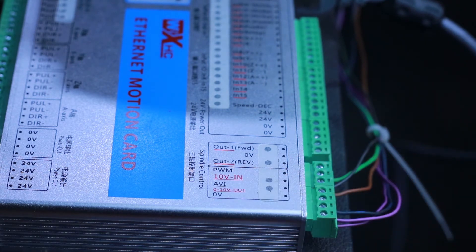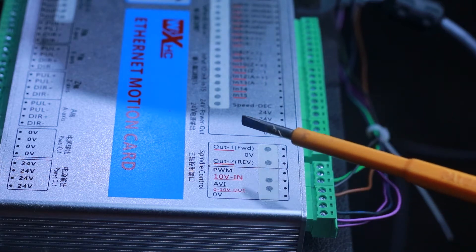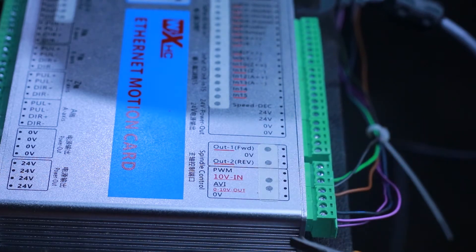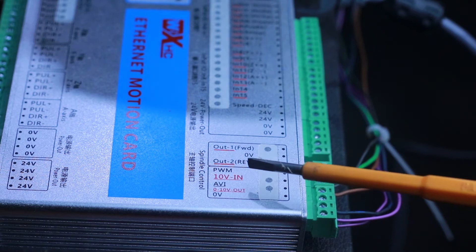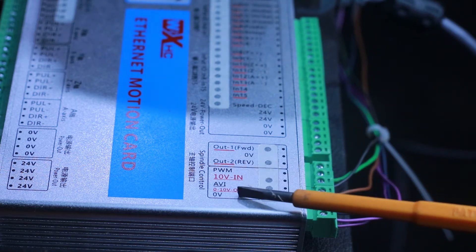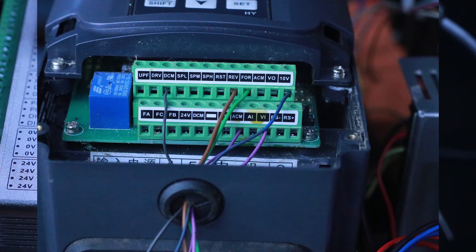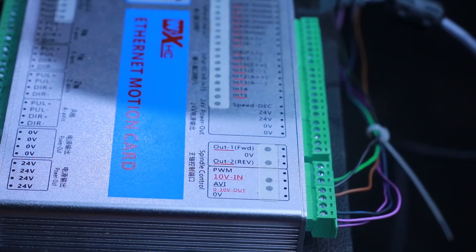As you must have noticed, we have two types of ground on this particular controller: the digital ground and the analog ground. On our VFD we have two types of ground as well: the DCM which is the digital ground, and the ACM which is the analog ground.